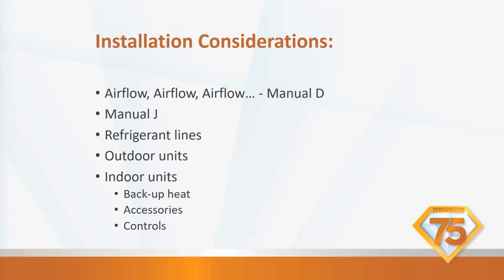We're going to talk a little bit about refrigerant lines, outdoor units, indoor units. There's things that we have to do before we even set the equipment. Looking up the correct equipment, checking what our airflow is going to be with accessories, even backup heat. It reduces our airflow through the air handler. So we need to know what size so we can calculate into our ductwork and our jobs, whether it be new construction or retrofit. We still need to know what the airflow going through the system is so that we can offer other things if we need to.